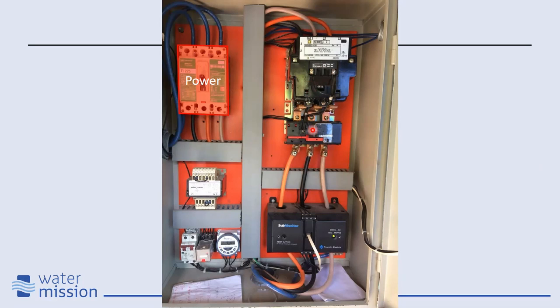Now, you could say that that is a part of the control circuit because it's sensing some type of environmental input and then relaying a signal to the contactor, and the contactor is what disconnects the pump. But I've included it here as part of the contactor assembly because it is almost always done that way, and it's going to be directly beneath the contactor. So now, I ask you guys to find where is the control circuit on this.